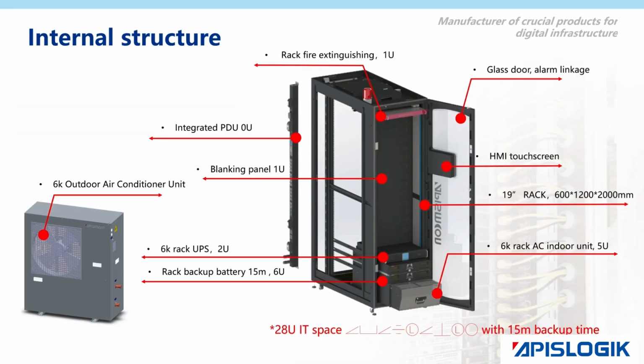At the bottom, a 5U rack-mounted AC indoor unit with 6 kilowatts cooling capacity, 3 to 7U smaller than a typical 6 kilowatts rack AC. It can use natural cooling sources to improve energy saving. It can accommodate rack UPS systems with capacities of 6 kVA, 10 kVA, and 20 kVA. Modular backup battery can be configured, with each module occupying 3 U of space. For a 6 kVA system with a 15-minute backup time, 2 sets of battery modules are required, taking up 6 U of space.